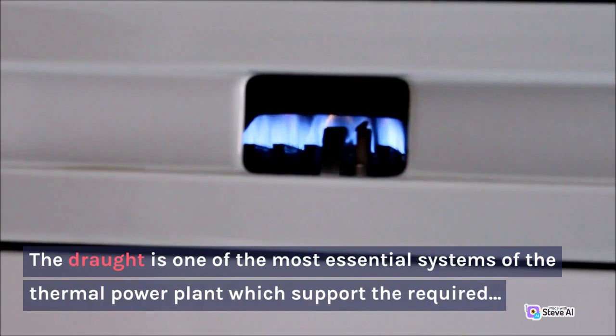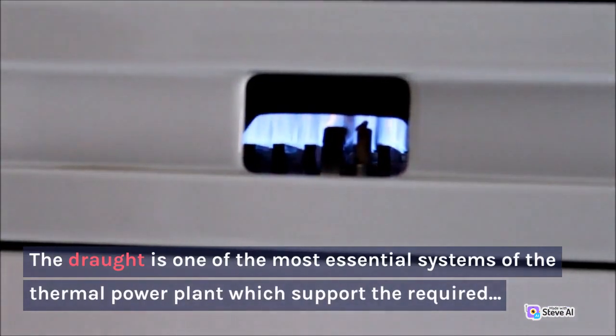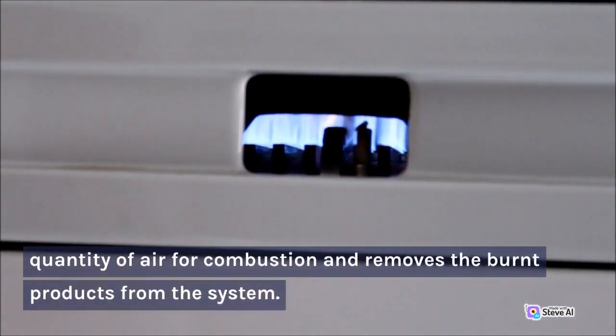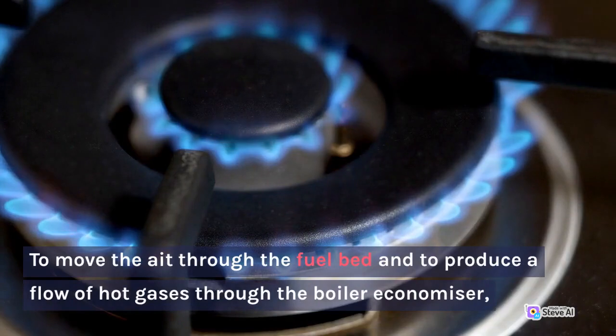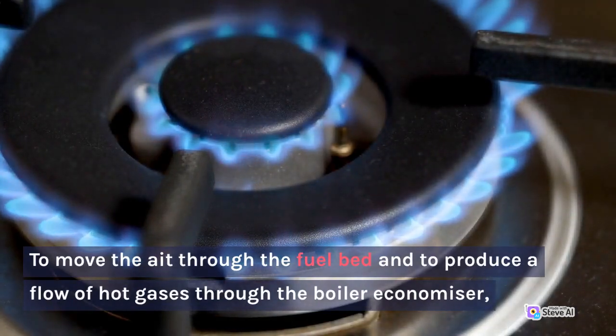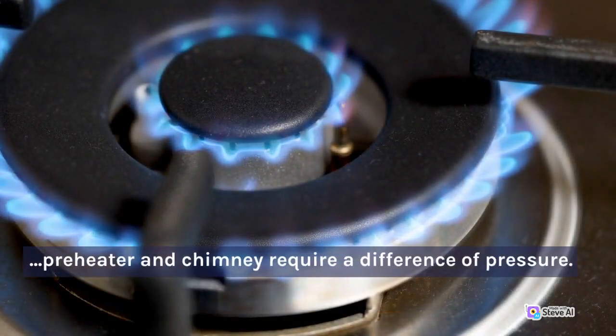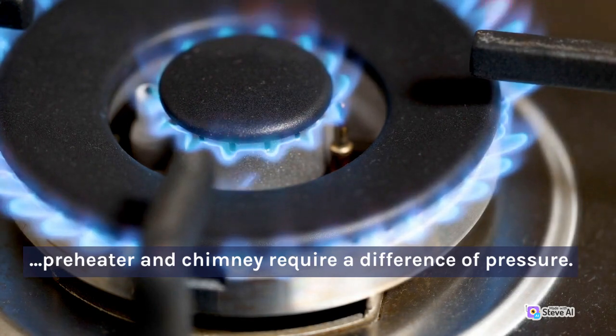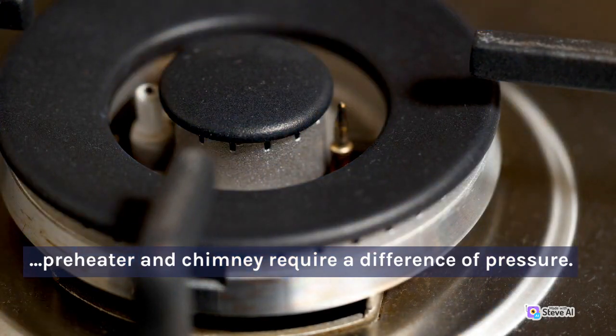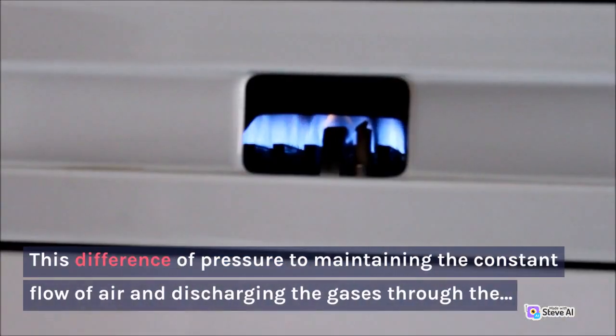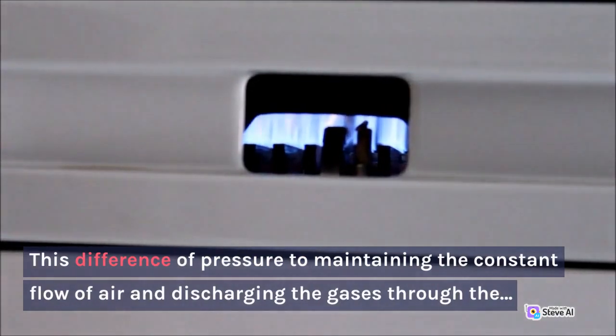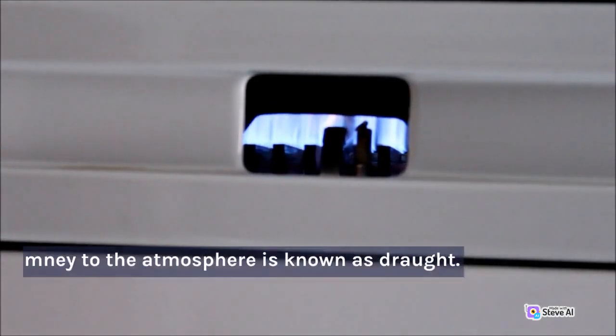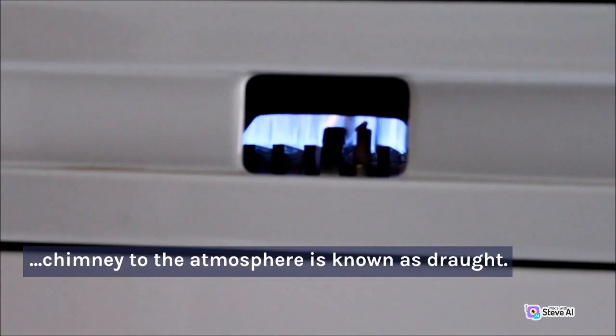The draft is one of the most essential systems of the thermal power plant which supplies the required quantity of air for combustion and removes the burnt products from the system. To move the air through the fuel bed and to produce a flow of hot gases through the boiler, economizer, preheater and chimney requires a difference of pressure. This difference of pressure, maintaining the constant flow of air and discharging the gases through the chimney to the atmosphere, is known as draft.